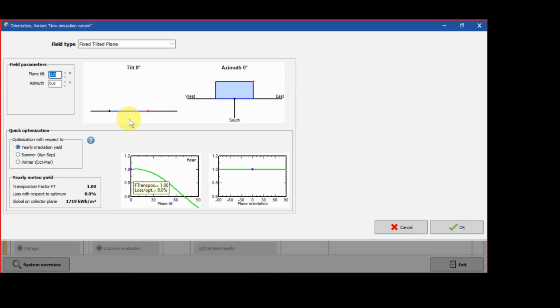Right? The perfect angle, the best angle by rule of thumb, is actually dependent on the latitude. Meaning, for example, in Malacca, 2 degrees, right? So the optimal angle, if you want to get maximum sunshine throughout the year, is 2 degrees. But 2 degrees, if we measure, is too small. The slant is very low, almost negligible.